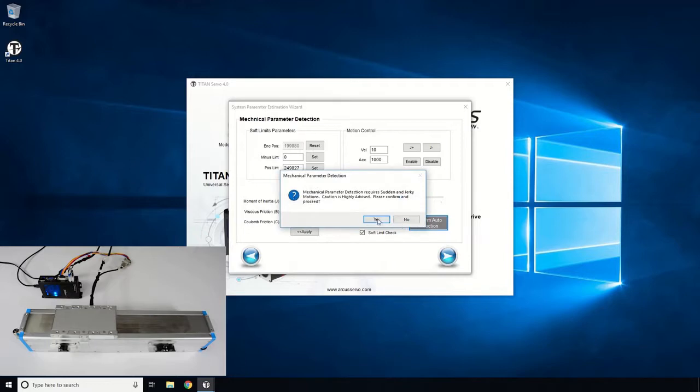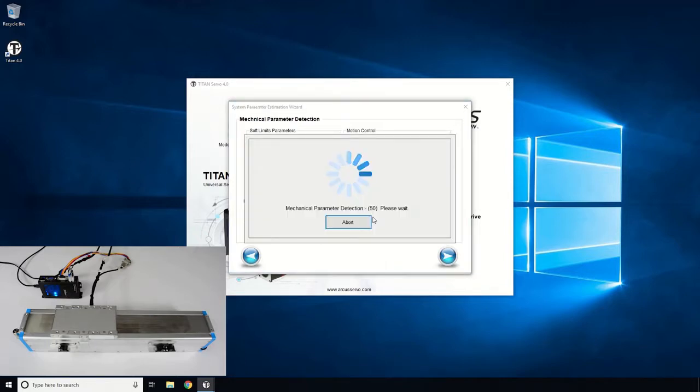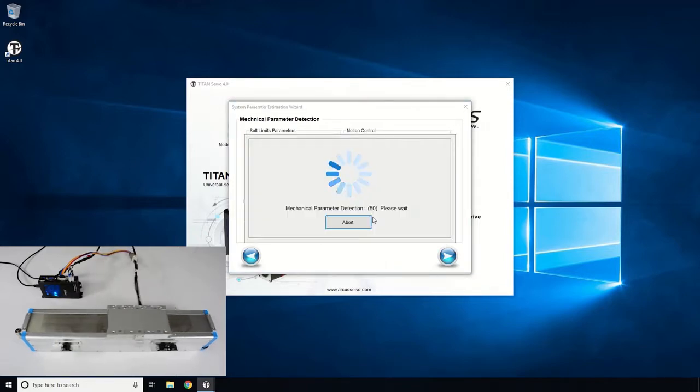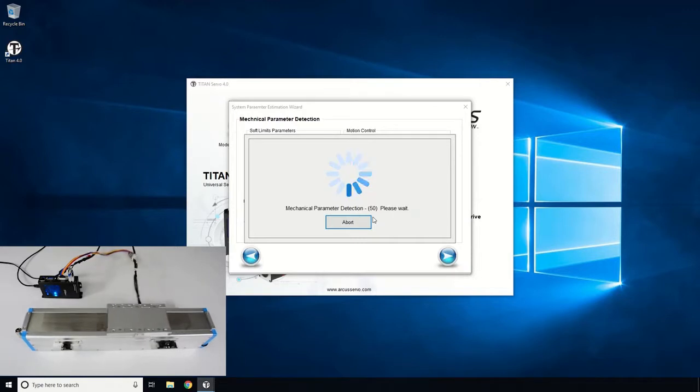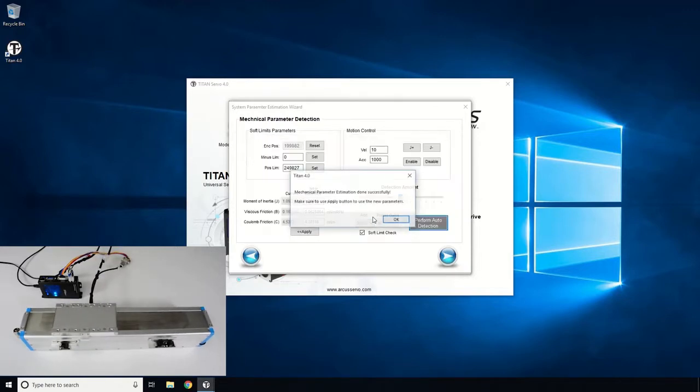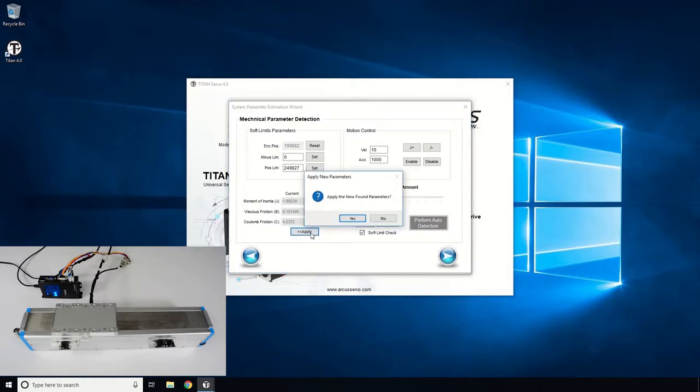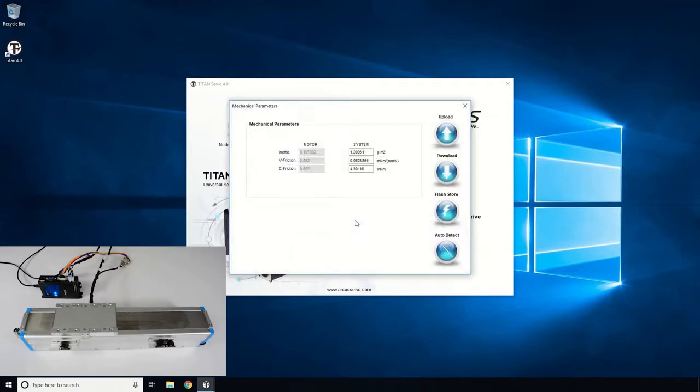Perform the Auto Detection sequence again and apply the values again. Click the Next button to finish the detection routine. We have now determined the motor inertia and the Coulomb and viscous friction values very easily within just a few minutes.